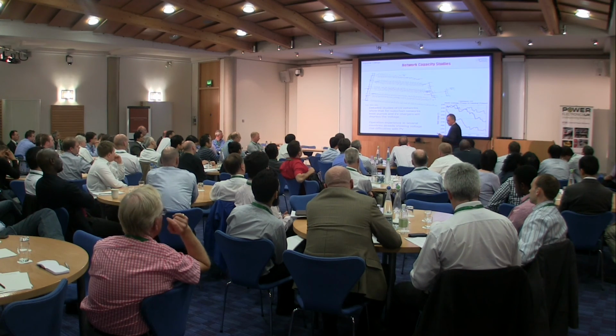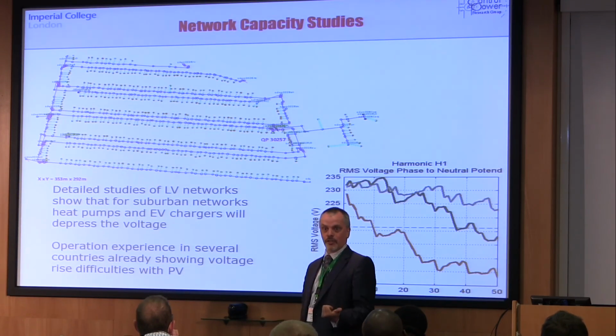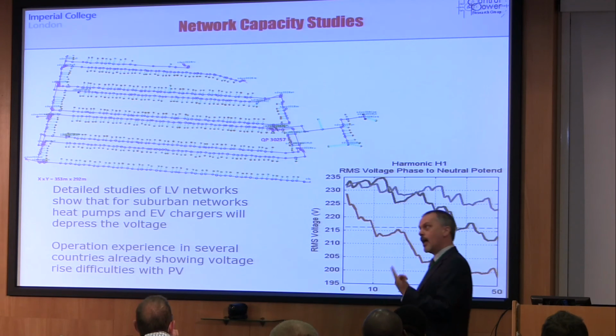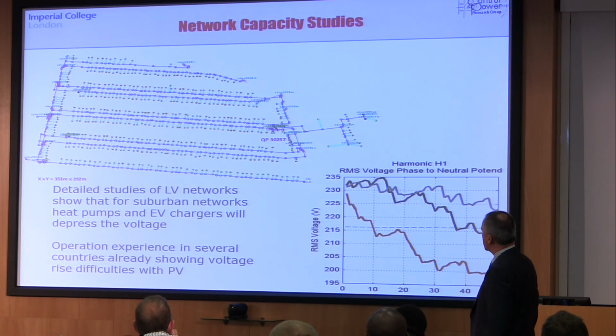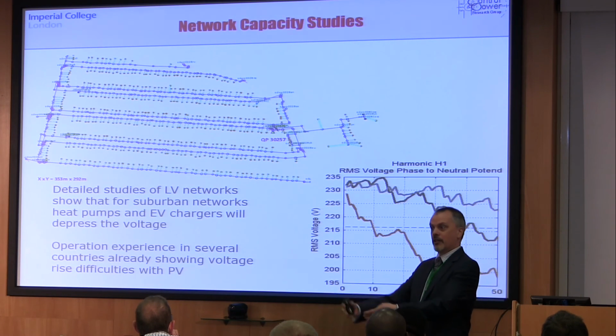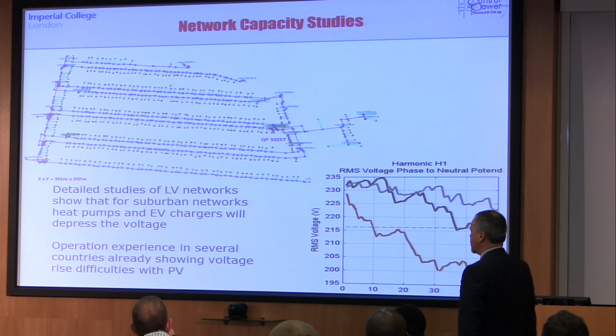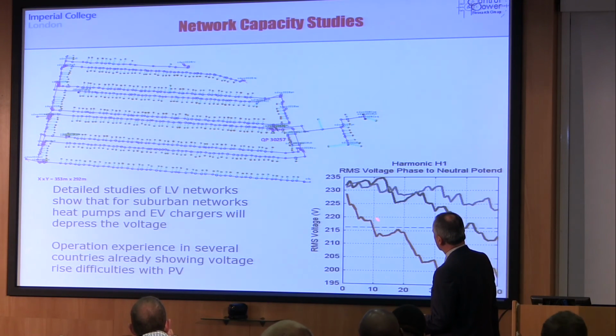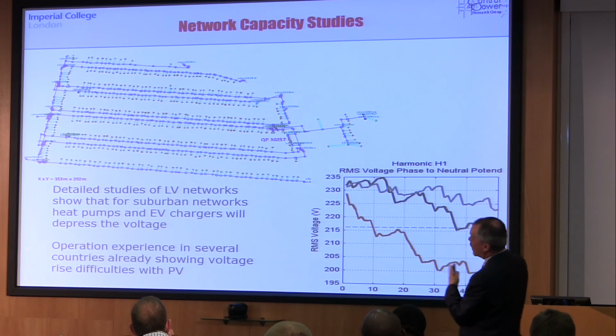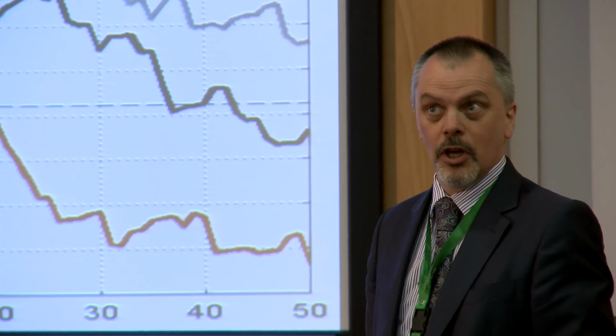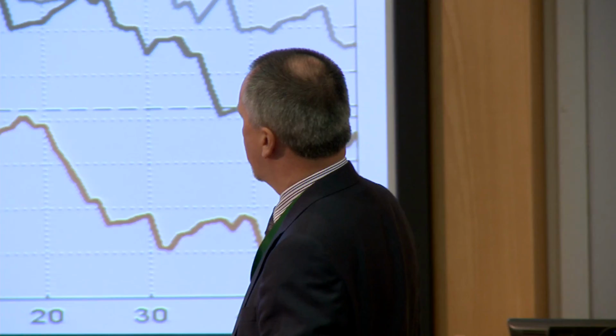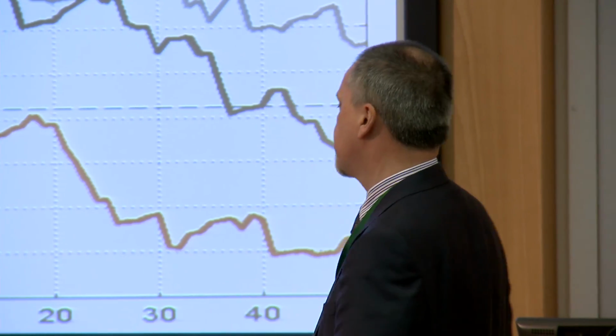There are two reasons for that. One is the UK practice of supplying single phase into houses, and the fact that houses are often not evenly distributed between the phases. If you complicate that by randomly putting heat pumps on that feeder, you can quickly find penetrations - this is a 20% penetration of heat pumps down that street - and you start threatening the lower voltage limit of the system.